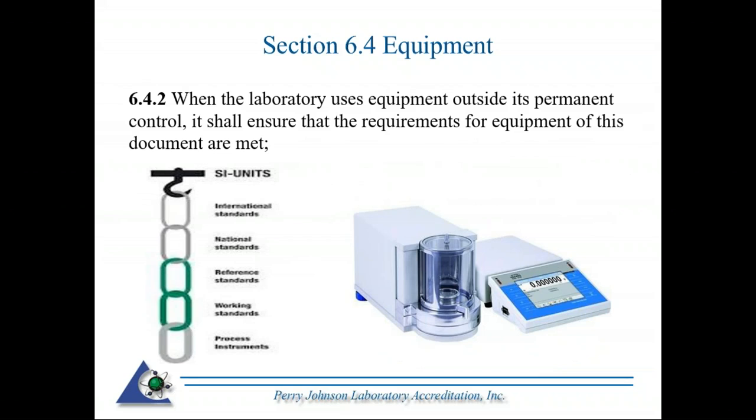When the laboratory uses equipment outside its permanent control, it shall ensure that the requirements for equipment of this document are met. One thing that comes to mind is if, for whatever reason, you had to use equipment that's not yours, perhaps yours is down, something you could rent or acquire, or that somebody else within the industry may allow you to use. First of all, there's traceability. If you're using equipment outside your permanent control, you have to assure that it's providing the traceability.